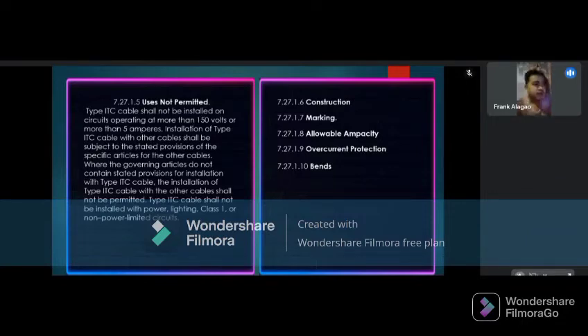Uses not permitted. Type ITC cable shall not be installed on circuits operating at more than 150 volts or more than 5 amperes. Installation of type ITC cable with other cable shall be subject to the stated provisions of the specific articles for the other cables. Where the governing articles do not contain stated provisions for installation with type ITC cable, the installation of type ITC cable with the other cable shall not be permitted.